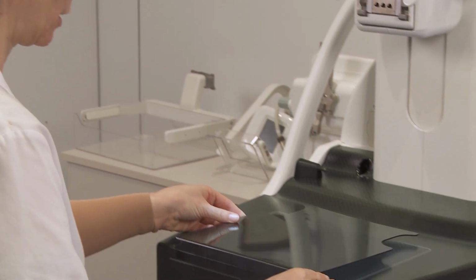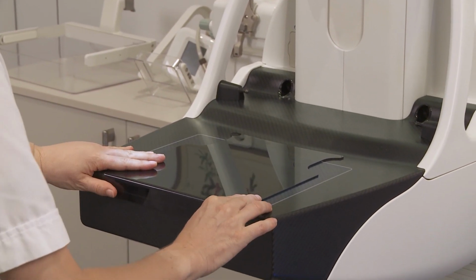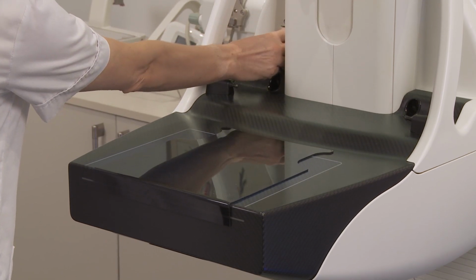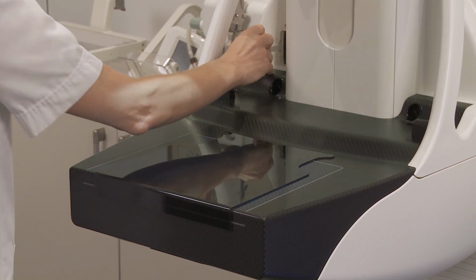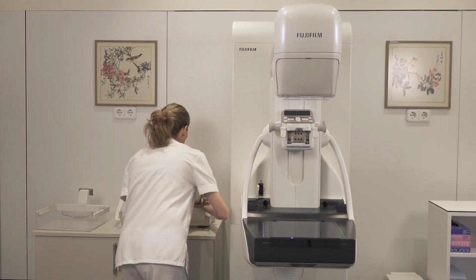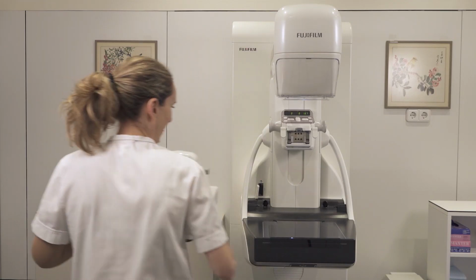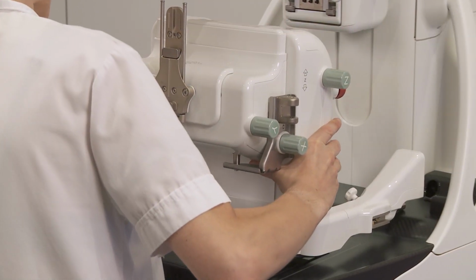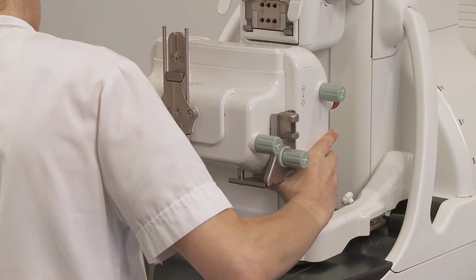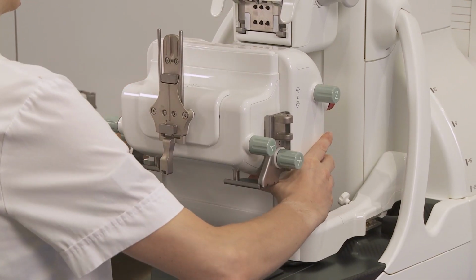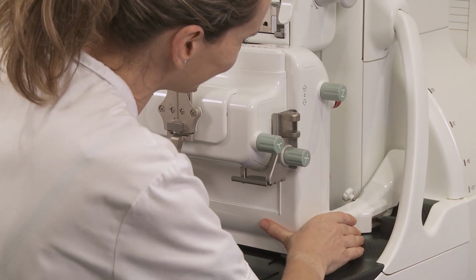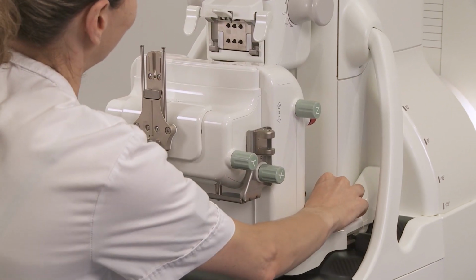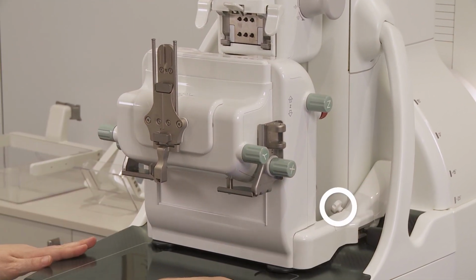Place the protective sheet over the breast support. Open the cover of the biopsy positioner connectors. The compressor paddle assembly position should be high enough for biopsy positioner insertion. Insert the biopsy positioner carefully into the dedicated holes in the gantry column and ensure the red section on the locks is not visible.